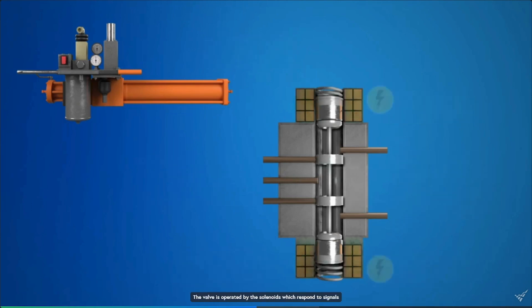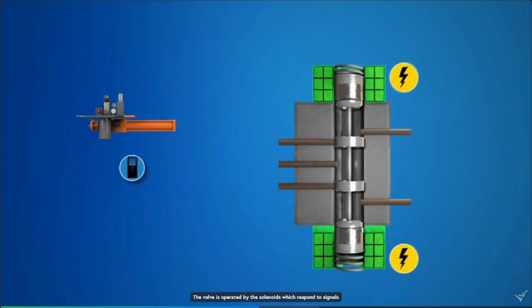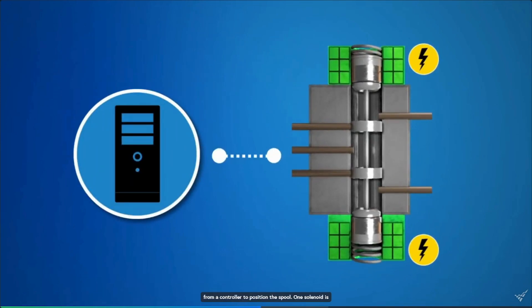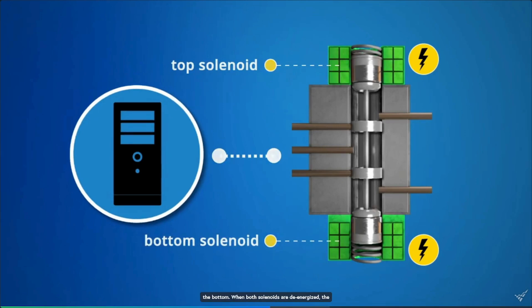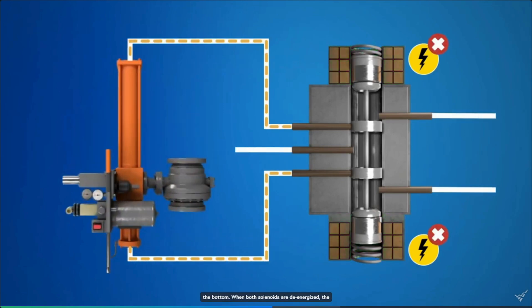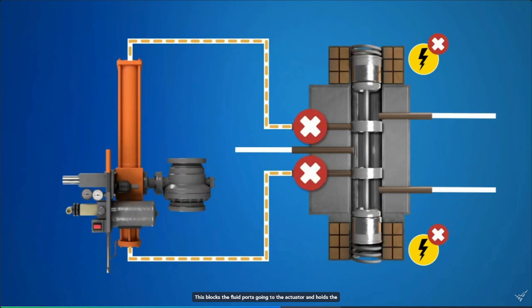The valve is operated by the solenoids, which respond to signals from a controller to position the spool. One solenoid is attached to the top of the spool and the other is attached to the bottom. When both solenoids are de-energized, the springs hold the spool in a neutral, or centered, position. This blocks the fluid ports going to the actuator and holds the actuator's piston in place.